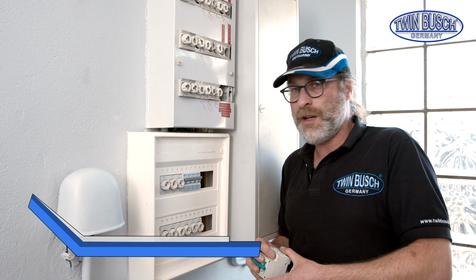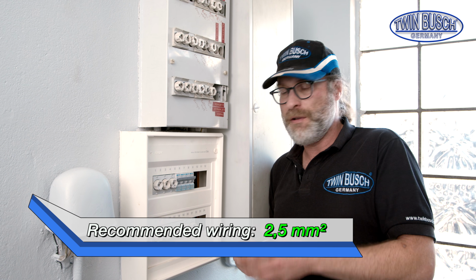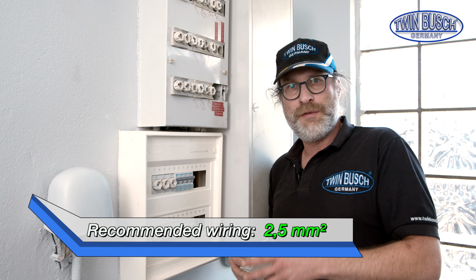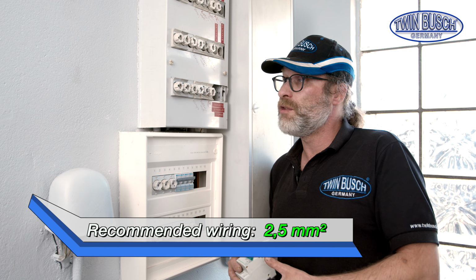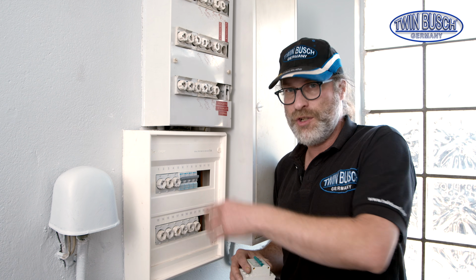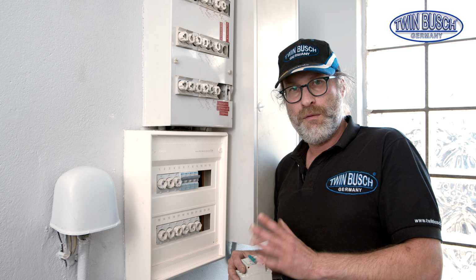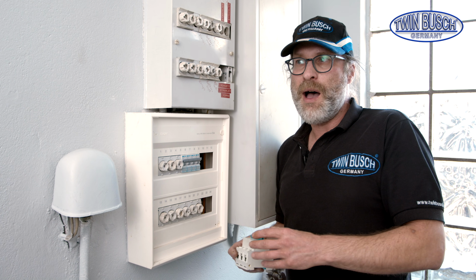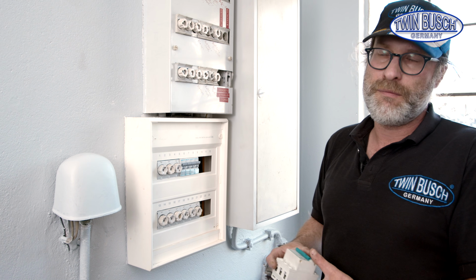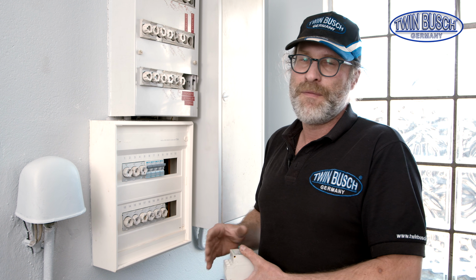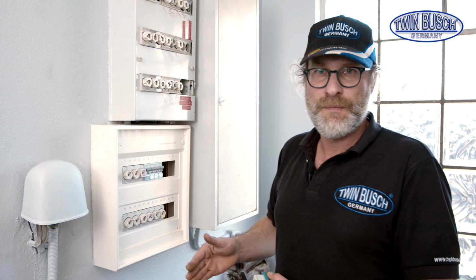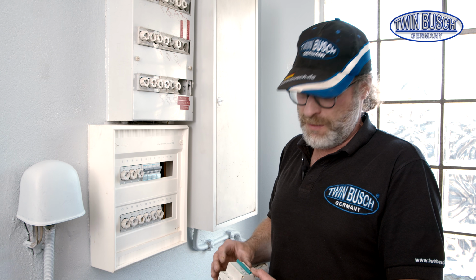In terms of cable cross-section, I generally recommend a cable cross-section of 2.5 square millimeters for new wiring. It depends a bit on the cable length. If you have short paths toward the circuit breaker or toward the fuse box sub-distribution, 1.5 square millimeters would also work. But it's been confirmed, when there's a cable reel or an extension cable in between which is not perfectly dimensioned, then at least the supply up to the outlet where the lift is operated, or a permanent connection, should be 2.5 square millimeters.